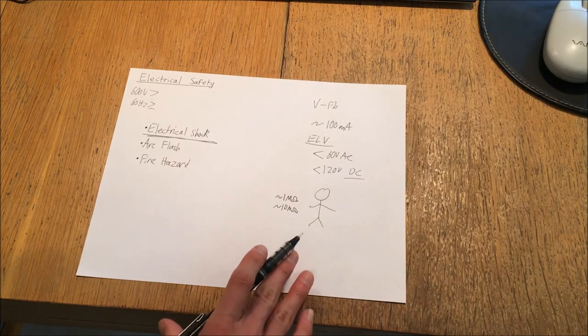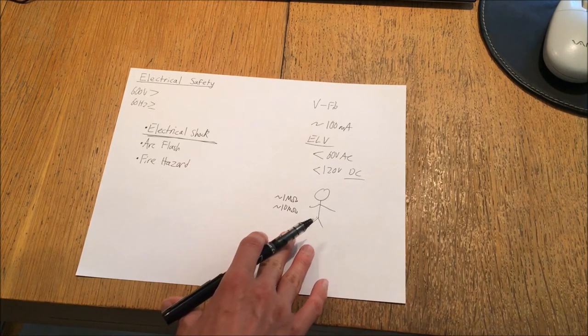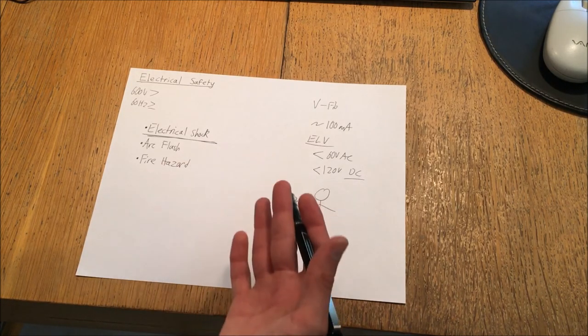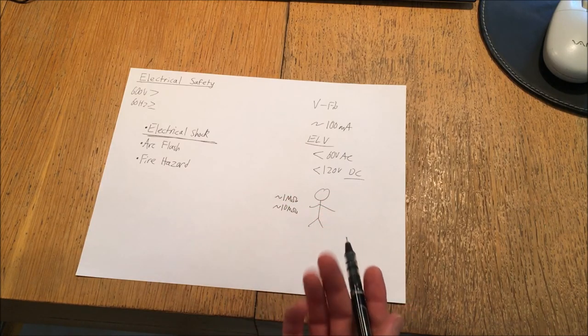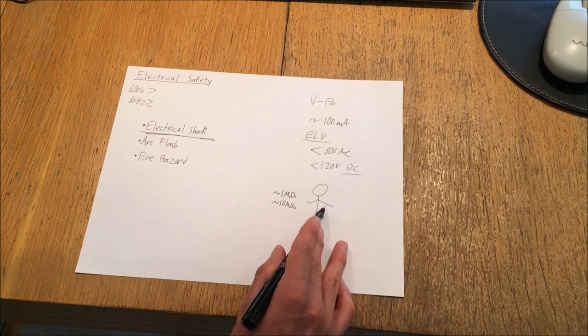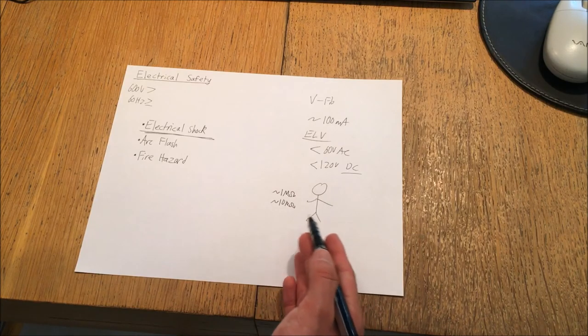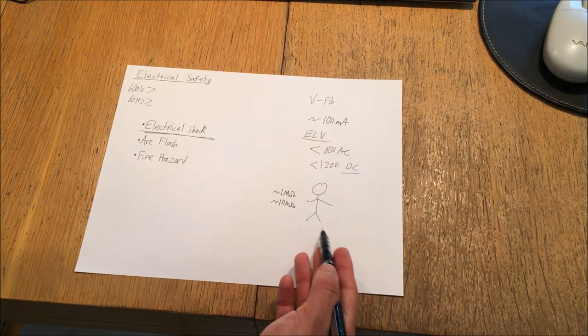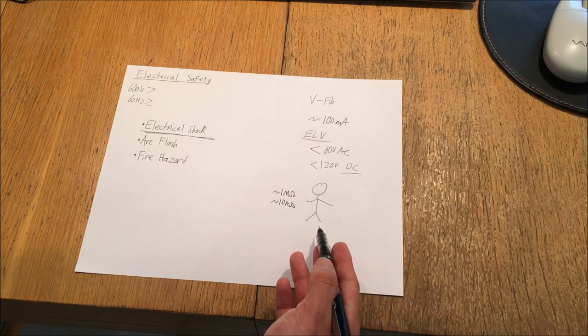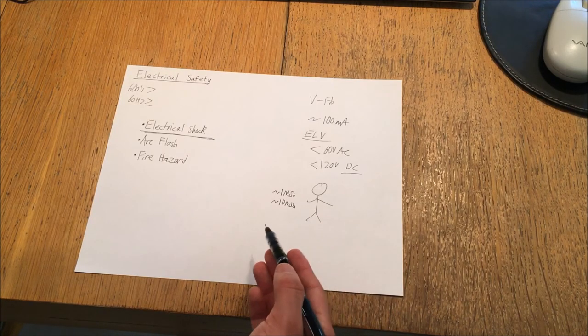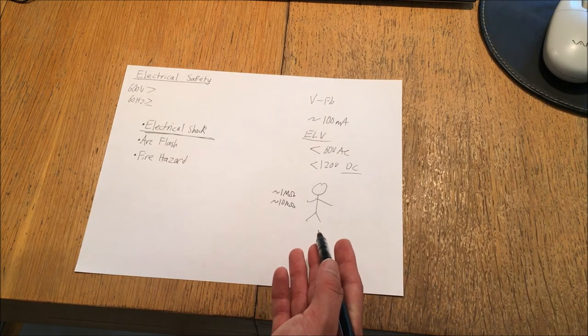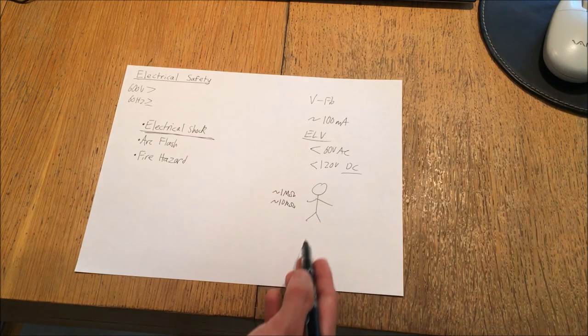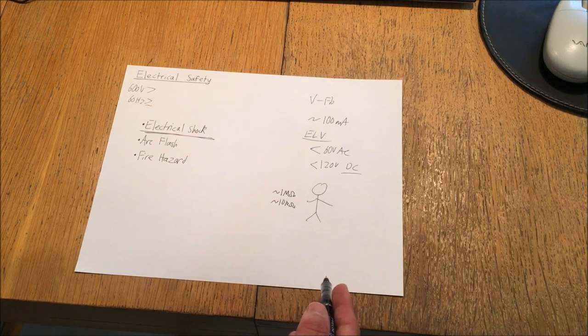This is one of the reasons why when working live only use one hand in the circuit at a time, because this eliminates the hazard of conducting current across your body and thus across your heart. Also be sure that you're not standing on something wet or conductive like a metal plate or a puddle of water on concrete because this could conduct current through your body and through your legs.